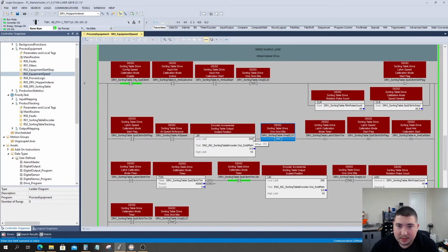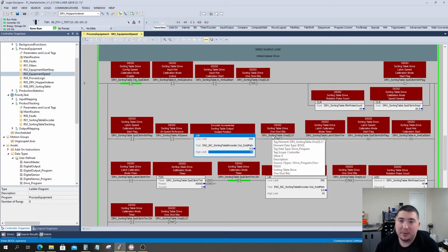It's the same logic, set up exactly the same way, but the only difference is that instead of an input from a singular sensor, we have to look at its relative position. The way I'm handling the encoder in this case is I'm changing its real position to a position in degrees. Because this is a cyclical axis, it will only ever be in a position of 0 to 360 degrees. So I have this limit instruction which will look at our relative position in the encoder, and when our value is between 350, which is our low, remember because below 0 we're going to reset to 360 and down, so 350 is our low and 10 is our high. As it goes up, we'll have a pulse for that 20 degrees of revolution.